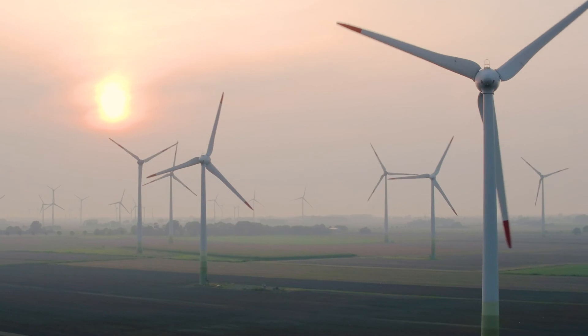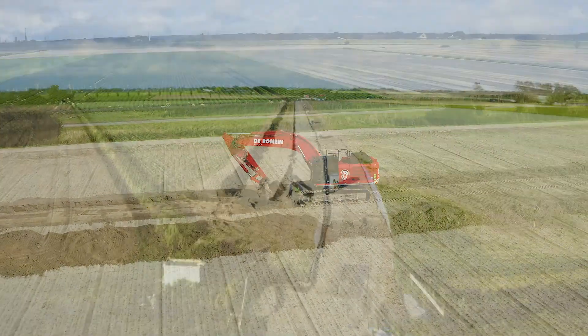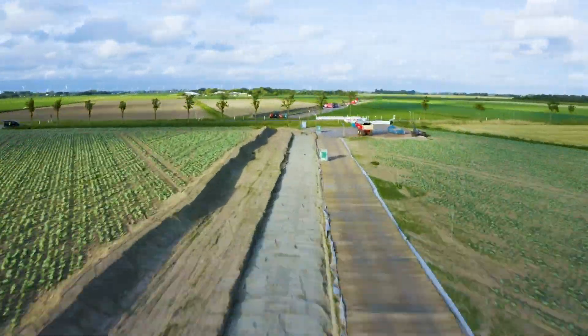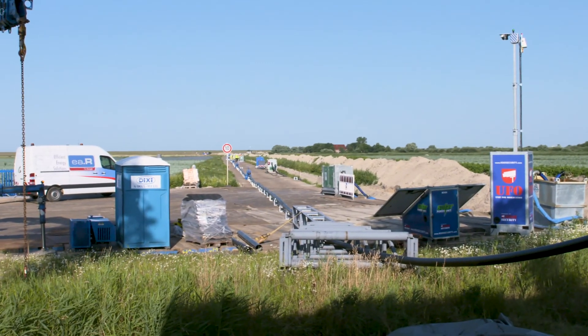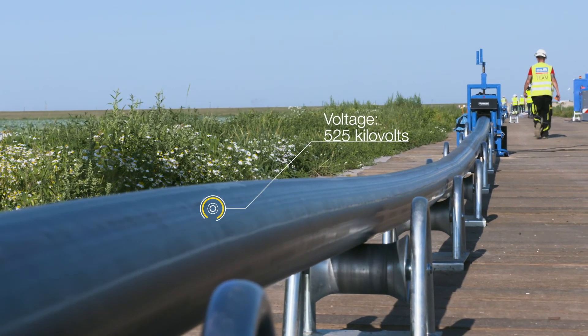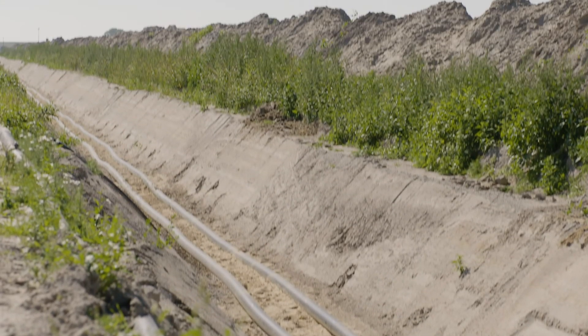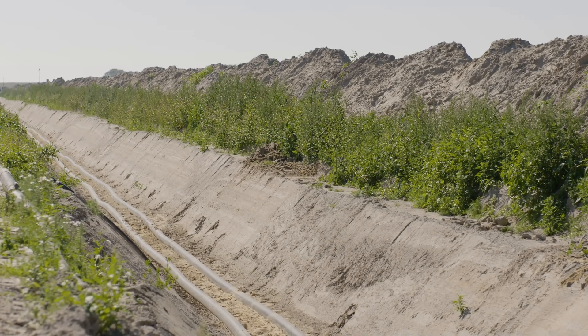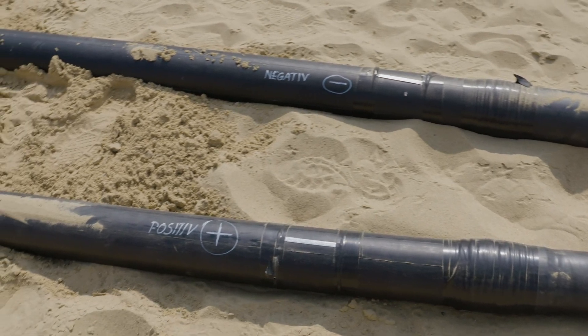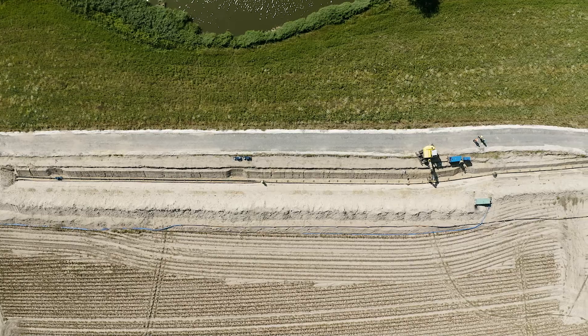TenneT is one of the most important investors in the energy transition and the builder of many new underground power lines. To transport electricity with minimal losses over very long distances, TenneT makes use of high voltage direct current transmission at a voltage of up to 525 kilovolts. For a transmission capacity of 2 gigawatts, one cable pair is used, consisting of a positive and a negative pole. The two cables can then theoretically supply 5 million households with electric power.